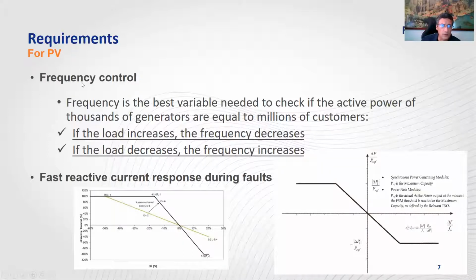Normally, PV doesn't pay too much attention to this requirement, but of course, if you have this PV on the distribution grid on your rooftop, it's not a big issue. But if we have this kind of plant all over the country, connected to the transmission grid and taking over from all the synchronous machines, this requirement is vital to keep the lights on. Okay. There are also some requirements that are too technical, but typically there is a fast reactive current response during faults, where they have to respond in milliseconds, and here also in the frequency, in seconds.